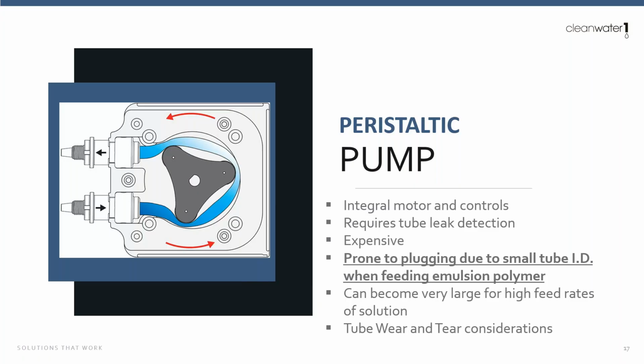and potentially plugging it. In regards to solution metering pumps for a dry polymer system, depending on your flow rate, these pumps can get very large. So footprint is something to consider there. And then again, the cost of these pumps at those large flow rates as well can get very high. One of the other considerations with peristaltic pumps is selecting the correct tubing. Tube wear and tear needs to be considered. Generally, you're going to require a specific type of tubing for the polymer being fed. And that's really important, right? Because we can get into an issue where tubes need to be replaced quite frequently, and it can cause maintenance and operational concerns.